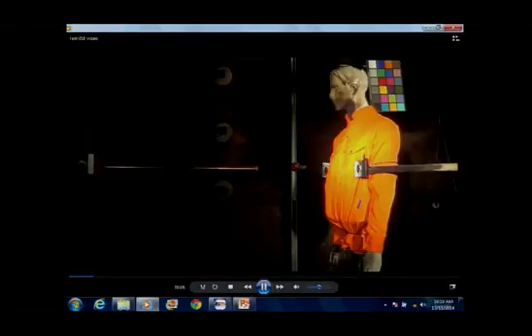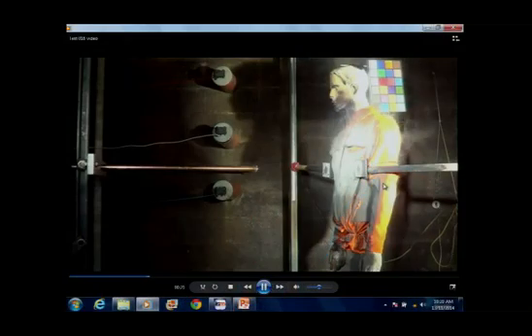Let's have a look then at the category 1 stuff, the supposedly unsafe category 1 because it doesn't meet the minimum 8 calorie mark. What we found is the result was very, very similar. So what we found was that the difference between cotton and arc-rated clothing was enormous. The difference between category 1 and category 2 was marginal. Very little difference in terms of actual protection.